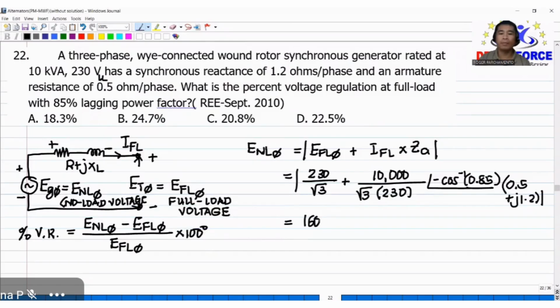So the no load voltage is equivalent to the magnitude of 230 over square root of 3, plus 10 times 10 exponent 3, the full load volt-ampere, over square root of 3 times 230, the line to line voltage, with angle negative arc cosine 0.85, since the power factor of the load is 0.85 lagging, multiplied by 0.5 plus 1.2j.